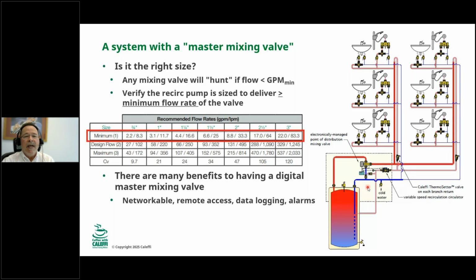And valves have minimum flow rates. So they have to see a certain amount of flow through the body of the valve where the sensing is to be able to operate properly. Why? If you have laminar flow coming into a valve and the cold and the hot are just coming in really slow, they can be too laminar for the sensor, and the sensor will see hot, it'll see cold, it'll see hot, it'll see cold, and the valve will hunt. But if you have enough flow, then you get nice chaotic turbulent flow around where the sensor is located. The valve will be steady and it will control.